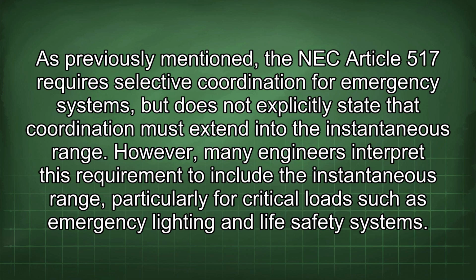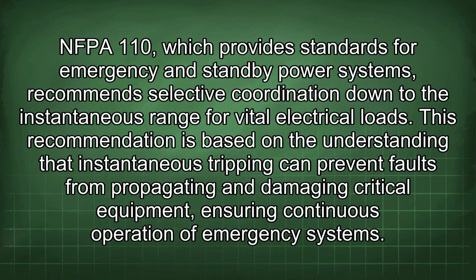life safety systems. NFPA 110, which provides standards for emergency and standby power systems, recommends selective coordination down to the instantaneous range for vital electrical loads. This recommendation is based on the understanding that instantaneous tripping can prevent faults from propagating and damaging critical equipment, ensuring continuous operation of emergency systems.